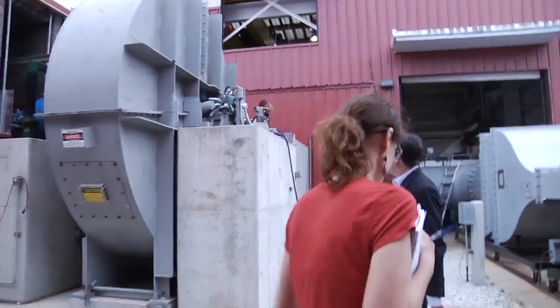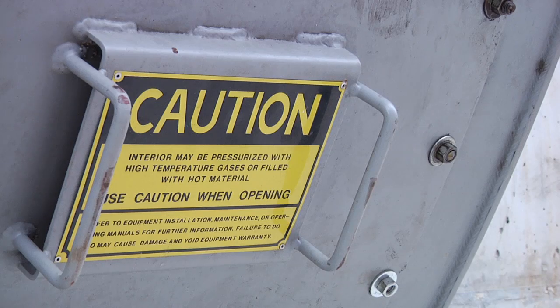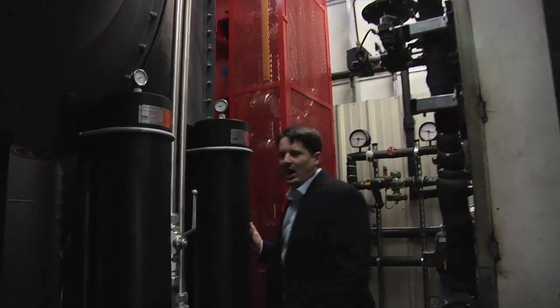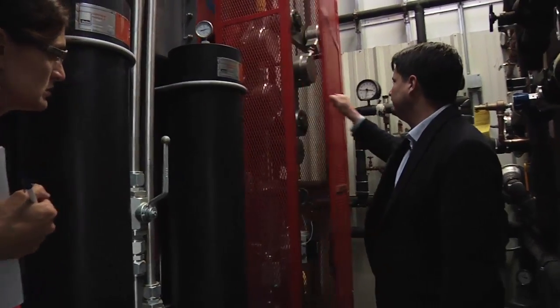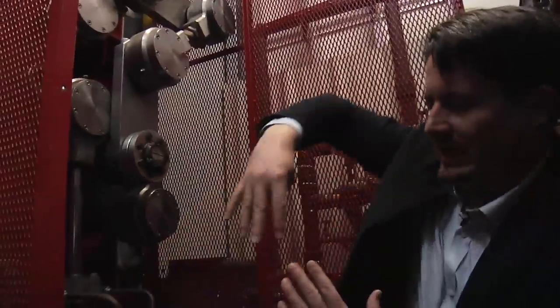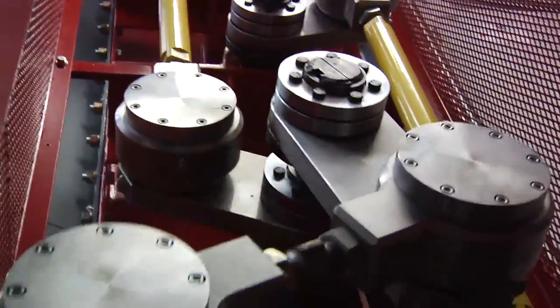So this is the fan. This fan assembly can produce 460 pounds per square foot of pressure at about 100,000 CFM leakage. We're standing in the area where the main control is located. It's a hydraulic system. Inside this red cage, we have a louver damper system. The louver damper has four paddles in there, and it can open, shut, and close in 0.16 seconds — it's incredibly fast.